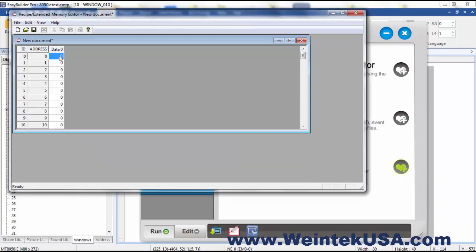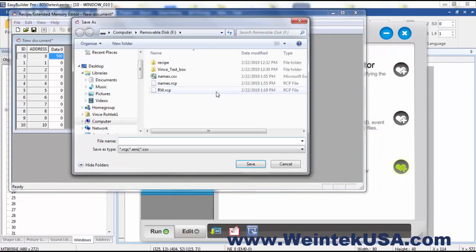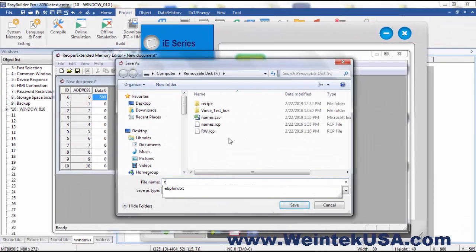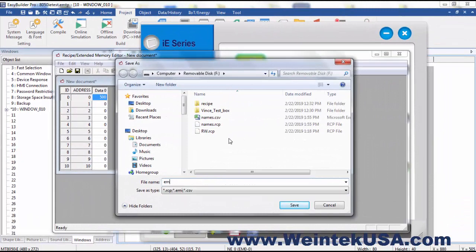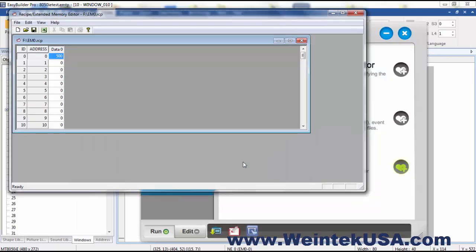And I want to put a value of let's say 500 in this register, and we want to go ahead and save it. And I'm saving it to a flash drive. Now this is the important thing: this file needs to be named the same as the memory extension for the extended memory. So as we did EM 0, we need to call this file EM 0 dot EMI, save.